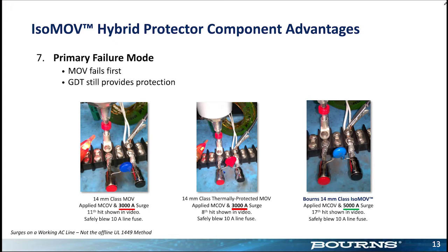Now, I keep talking bad about MOVs, but they're certainly better than nothing. And if you need to protect your device and you don't want to spend any money, the MOV is probably the first place to go. They're relatively inexpensive, and they do provide protection. And like I said, most of them by far don't have a problem with this kind of end-of-life phenomena, but some do. If you can't tolerate flaming, then a standard MOV is not what you were looking for.